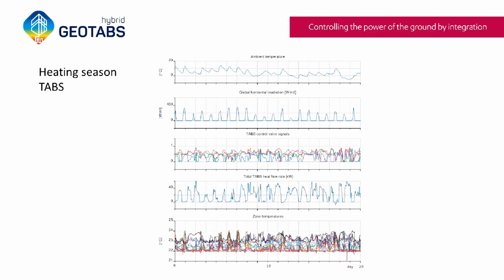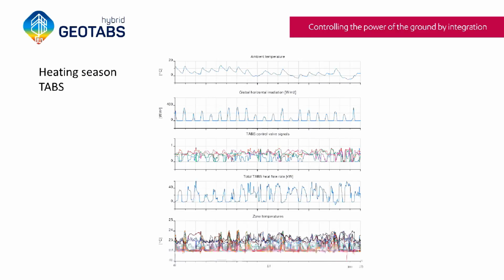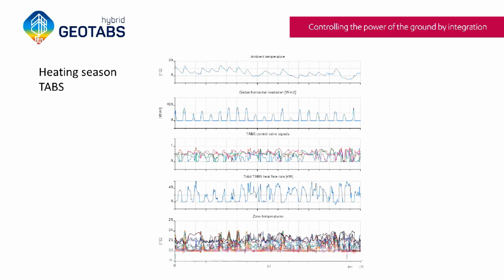At the top you see outdoor temperature, which goes sub-zero here, so it's a relatively cold period in Belgium that we're working on. Solar radiation is plotted here too, so there's still some sunlight. What we're essentially controlling is the two-way valves of the 4 floors, shown here with a lot of variation, captured in total by the heat flow rate flowing towards the TABS. You see a clear on-off behavior between day and night, where at night we need additional heating to keep the temperature above the lower bound of 22 degrees.